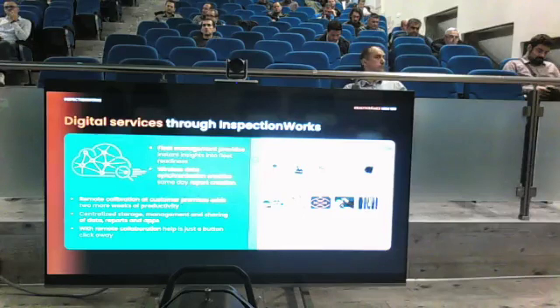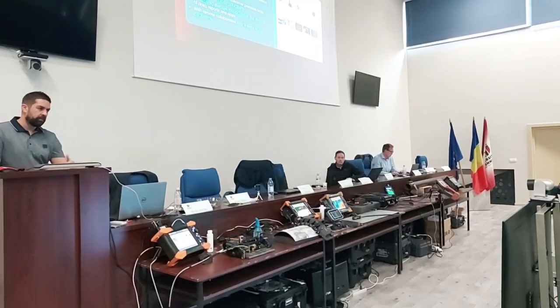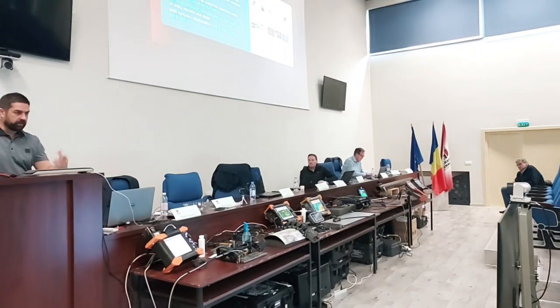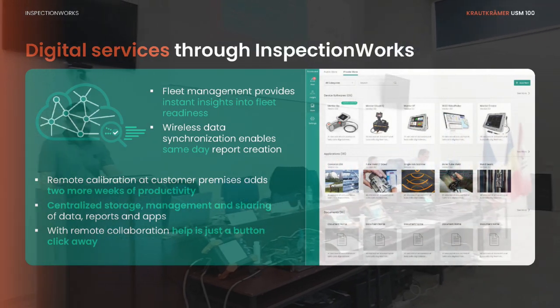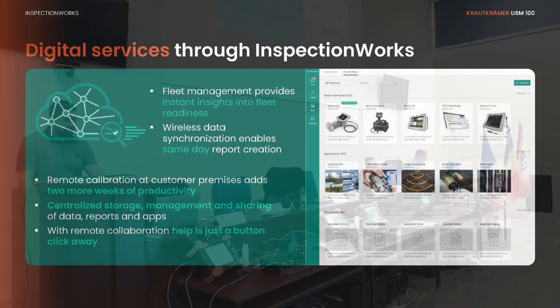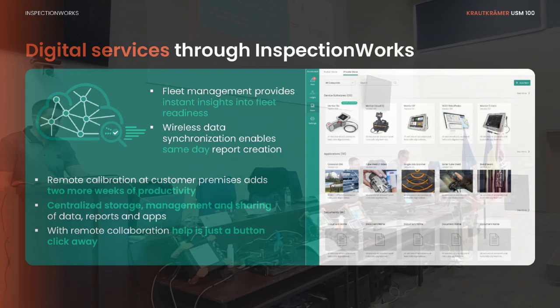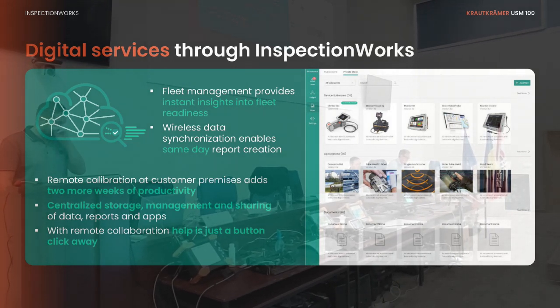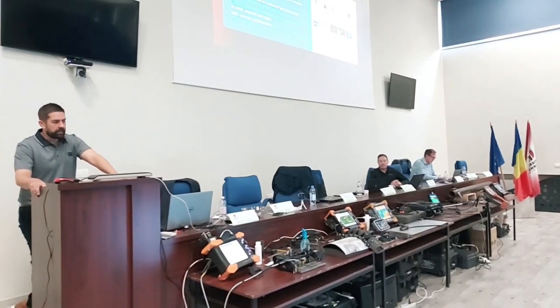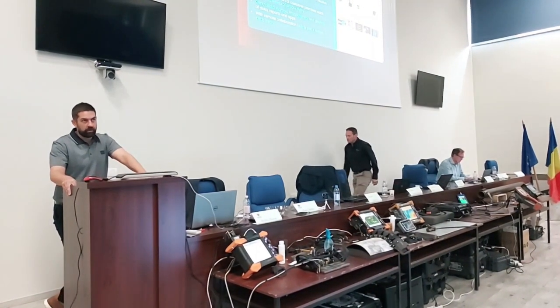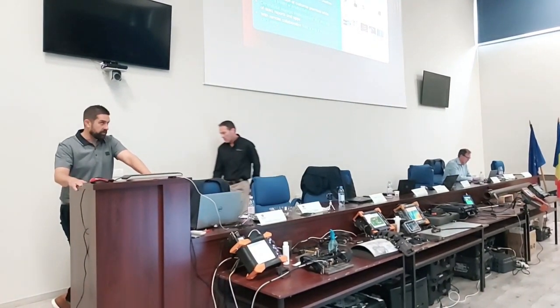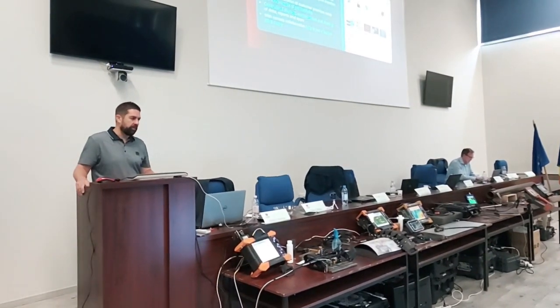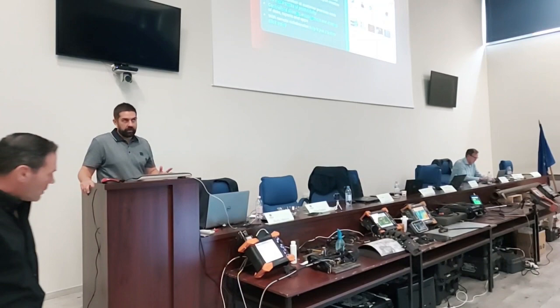We can automatically sync the device to have software updates. If you log into our encrypted cloud-based system, you can automatically update the USM 100 remotely. One of the benefits of this service is that the USM 100 can be calibrated remotely, so instead of having your device out of action for weeks, it can now be calibrated on site within an hour. This isn't an EN-ISO calibration, just a manufacturer's calibration, but it's a capability we're now offering with this device.